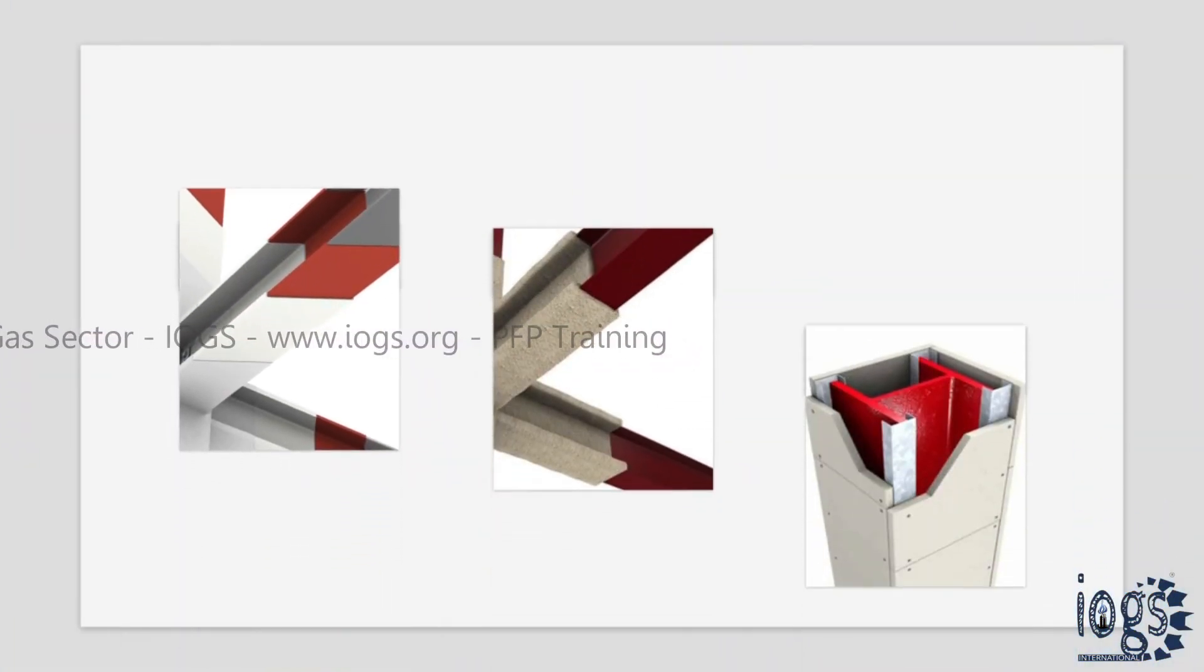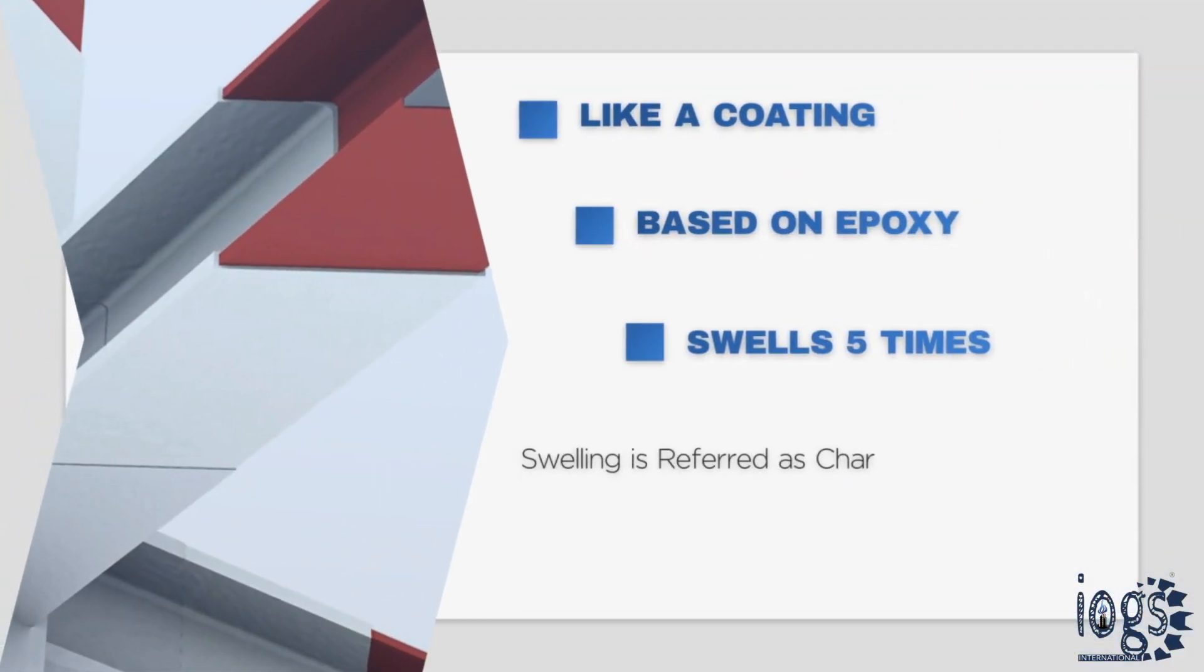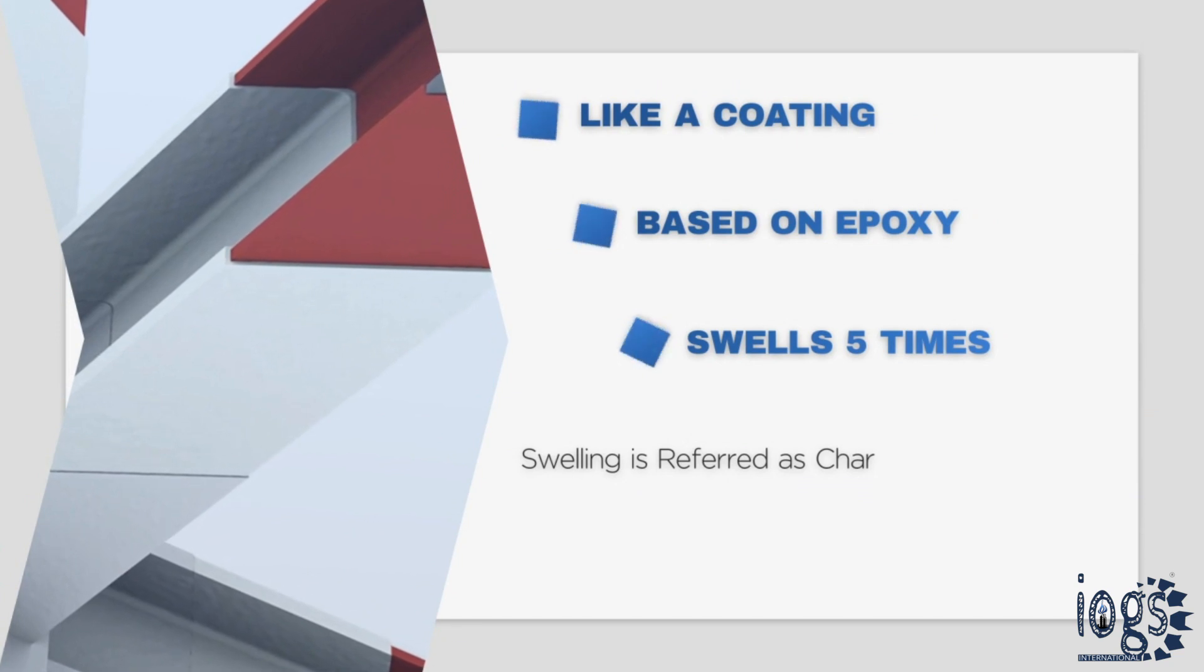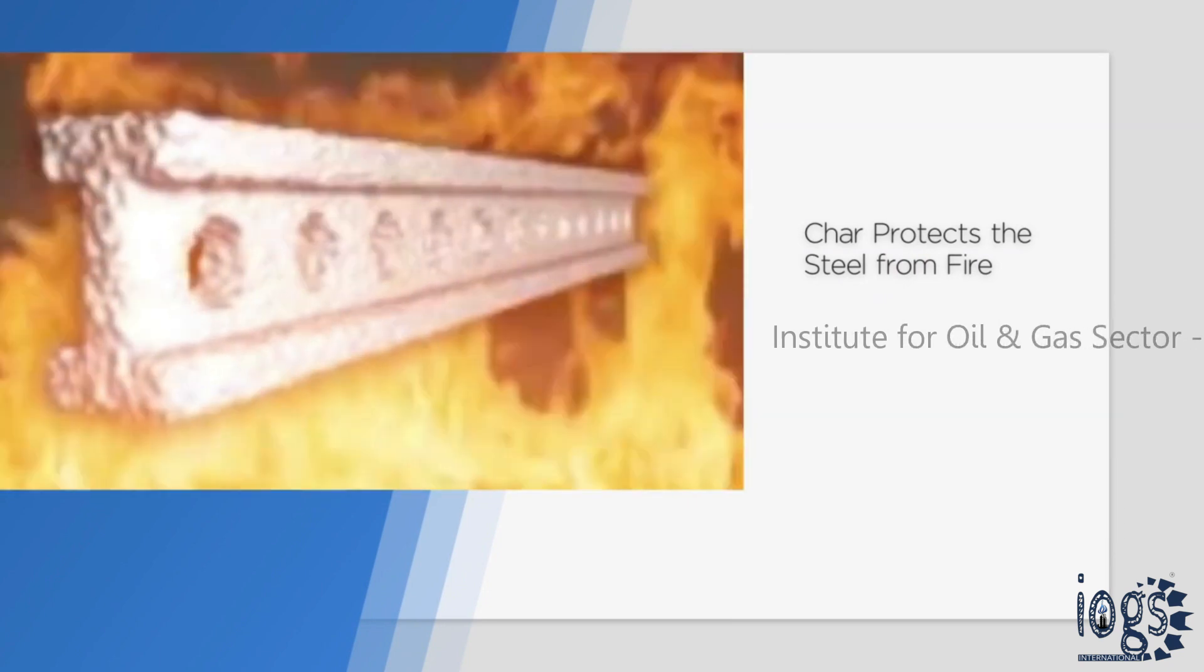Various fireproofing products can be used in making steel fireproofing. Intumescent fireproofing, often referred to as intumescent coating, is based on epoxy. The coating swells up to five times its original thickness to form an insulating char, and the char protects the steel from fire.